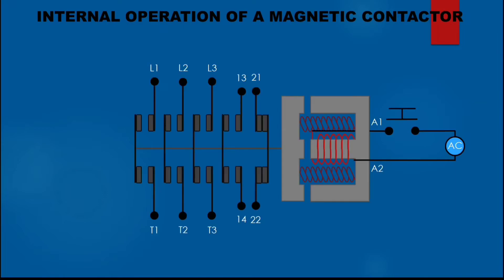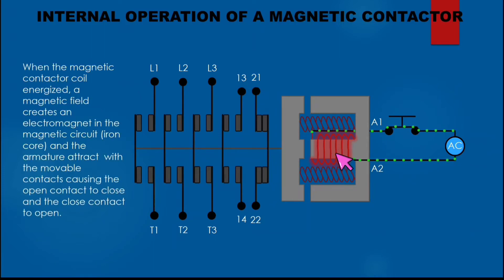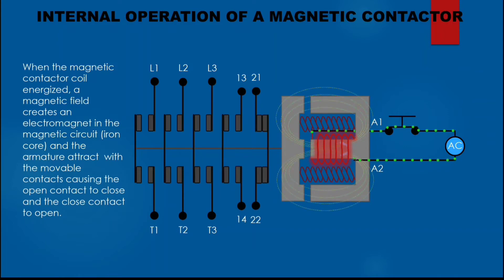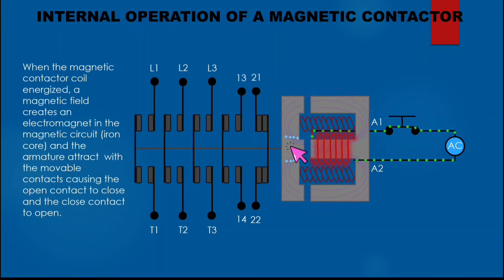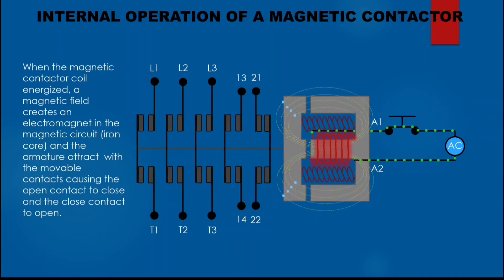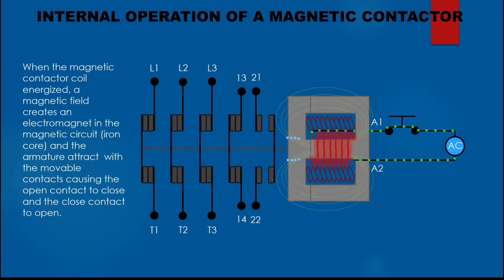Internal operation of a magnetic contactor: when the magnetic contactor coil is energized, a magnetic field creates an electromagnet in the magnetic circuit. The iron core and the armature attract with the movable contacts, causing the open contact to close and the closed contact to open.